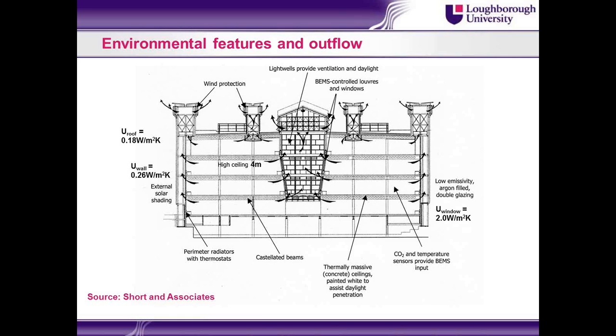A bit more information on the environmental features here. So up here on the top of the roof, these ventilation stacks have got wind protection, whereby rather than simply have a hole, we protect that hole by having semicircular, is it aluminium or steel? Semicircular metal devices for stopping the wind driving down into the ventilation stack. So the warm air flows up and out and finds its way around these semicircular cups, and the wind isn't able to drive down into the ventilation stack. I talked about the low driving pressures of buoyancy-driven natural ventilation. Wind is a threat to that. So in this particular design, we've designed the wind out of the solution, and we use just buoyancy to drive the flow.